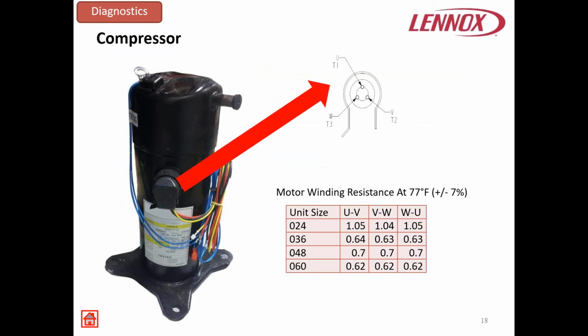While we're on the compressors, one thing to note, I talked about all 3 leads are going to virtually be the same. Here's your resistance windings across your compressor, and they're all a little different based on the tonnage. But what you'll see here, and I want you to really pay attention and really remember, not necessarily what the number is, but that all 3 are the same. Okay, they're really, really close. And as long as you have resistance across all 3 legs the same, a 3-phase compressor is different in that aspect. It doesn't have a start winding necessarily. So they're all going to be the same as far as resistance goes.